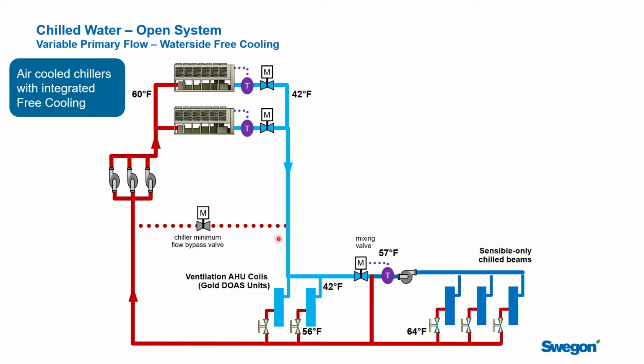And in the summer, in the cooling load season, we would make somewhere between 42 and 44 degree water to service the ventilation units. This water has to be cold enough to be able to do the dehumidification that the building requires. And then we would have a second loop that's servicing the chill beams. That's these characters right here. That loop's going to be above the dew point of the space, so it's typically 57 or 58 degrees, and we're sending water out here that is warmer to service this because we're only going to be doing sensible cooling out at the chill beams.